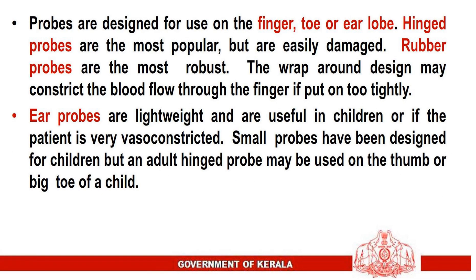Probes are designed for use on the finger, toe, or ear lobe. Hinged probes are the most popular but are easily damaged. Rubber probes are the most robust. The wrap-around design may constrict blood flow through the finger if put on too tightly. Ear probes are lightweight and useful in children or if the patient is very vasoconstricted. Small probes have been designed for children, but an adult hinged probe may be used on the thumb or big toe of a child.